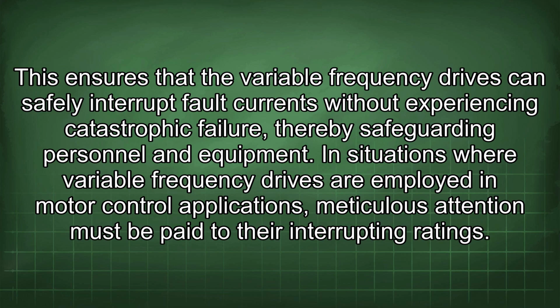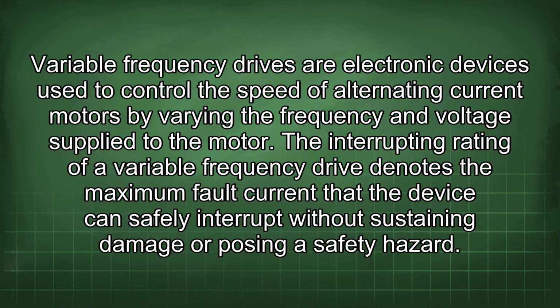In situations where variable frequency drives are employed in motor control applications, meticulous attention must be paid to their interrupting ratings. Variable frequency drives are electronic devices used to control the speed of alternating current motors by varying the frequency and voltage supplied to the motor. The interrupting rating of a variable frequency drive denotes the maximum fault current that the device can safely interrupt without sustaining damage or posing a safety hazard.